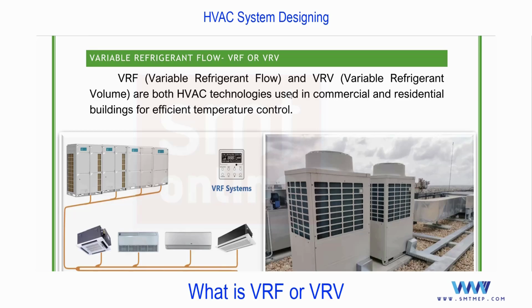At this level, remember DX system means the refrigerant is responsible to cool the air, compared with the chilled water system. So VRF also comes under DX system. And in VRF, if you compare this VRF with the split system, the major difference is, in a split AC or ductable split, you can connect one indoor to one outdoor. But in case of VRF or VRV, we have the option to connect multiple indoors to one outdoor.